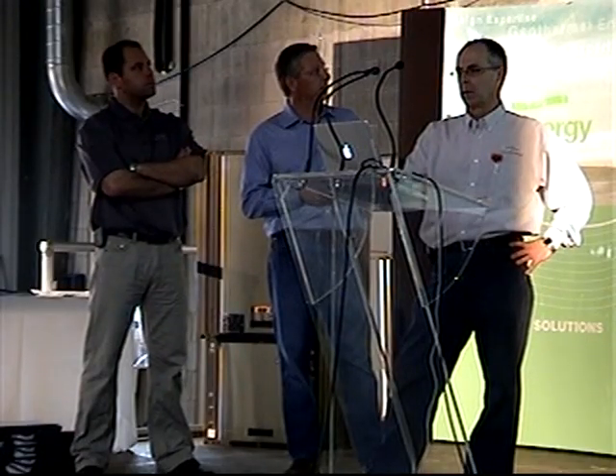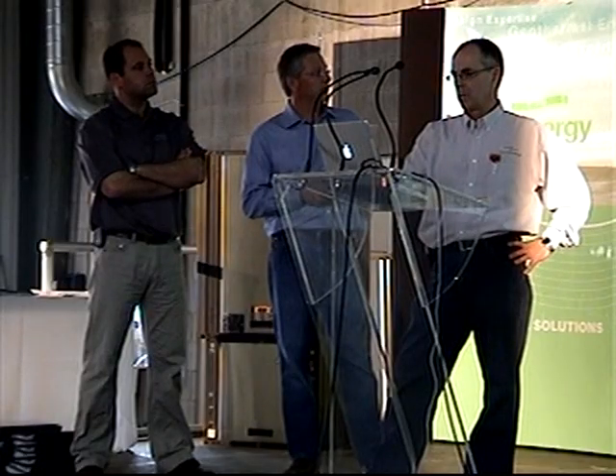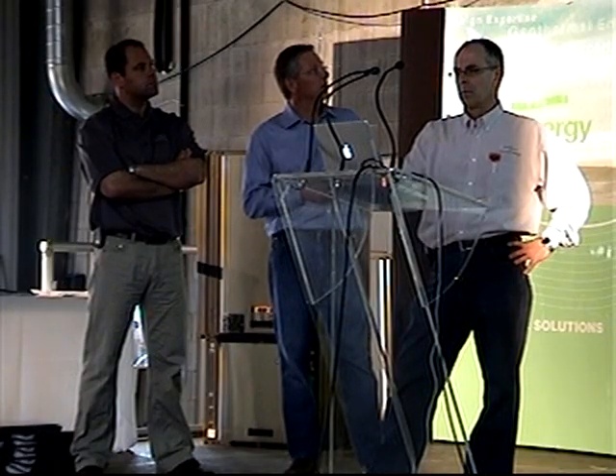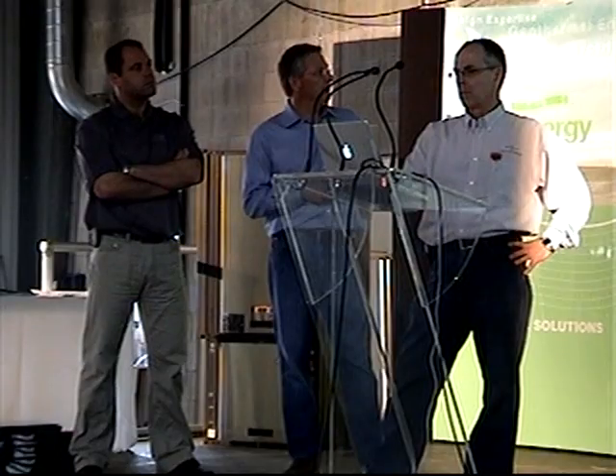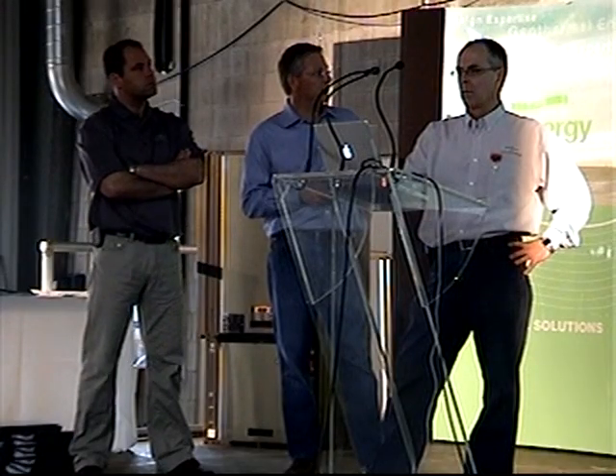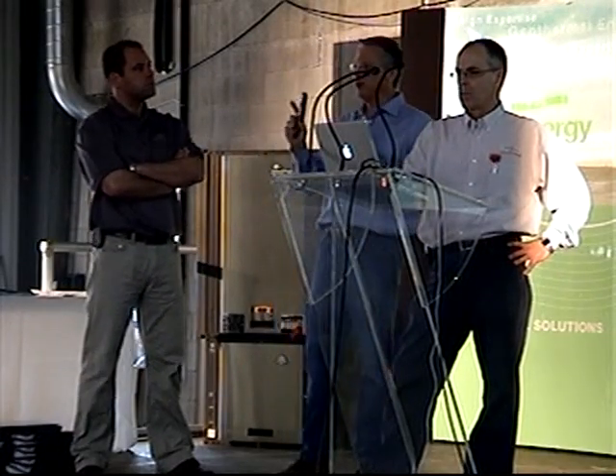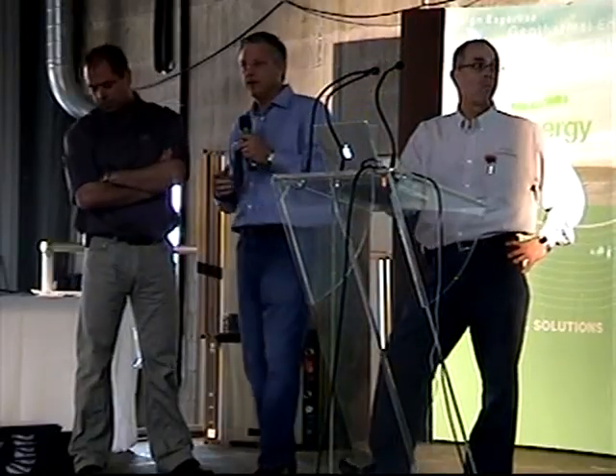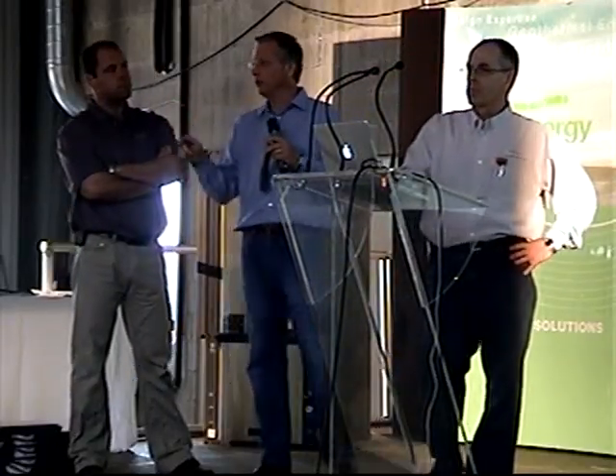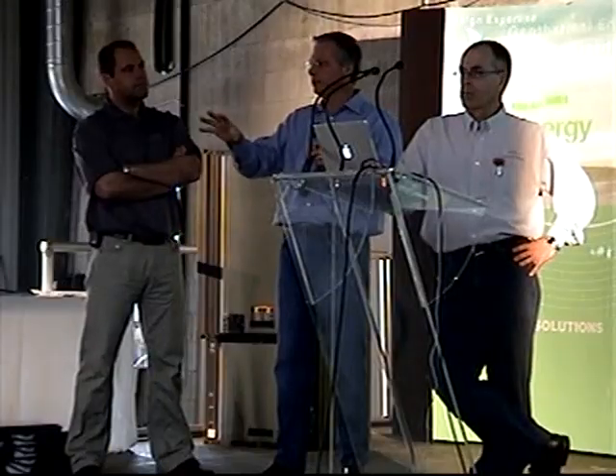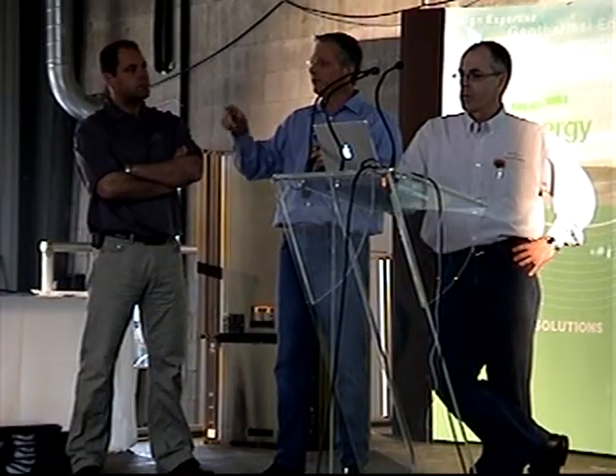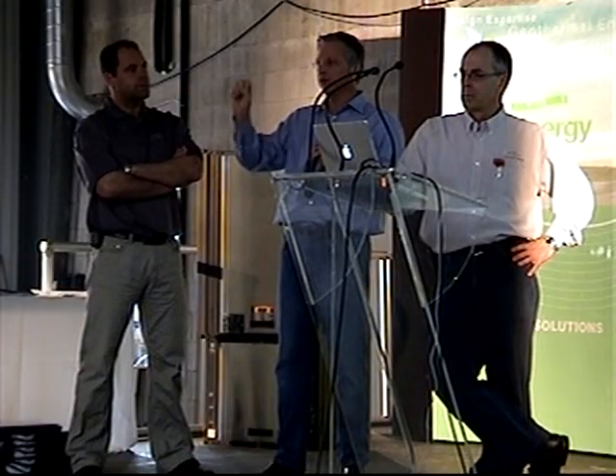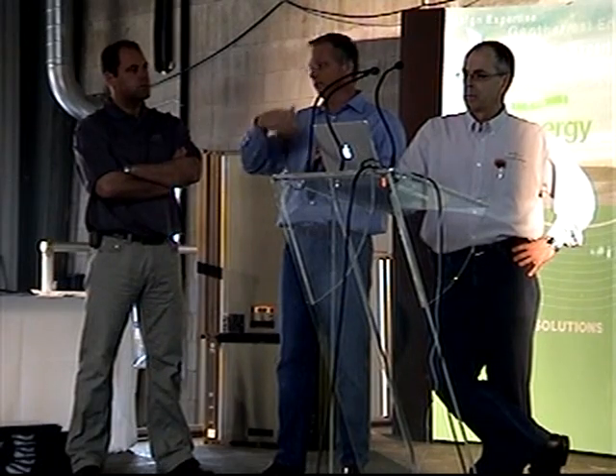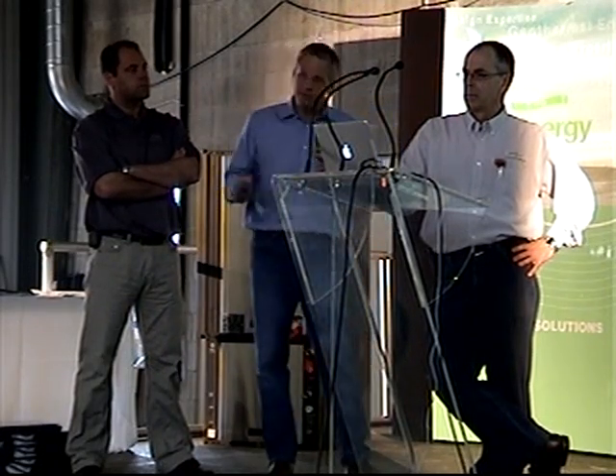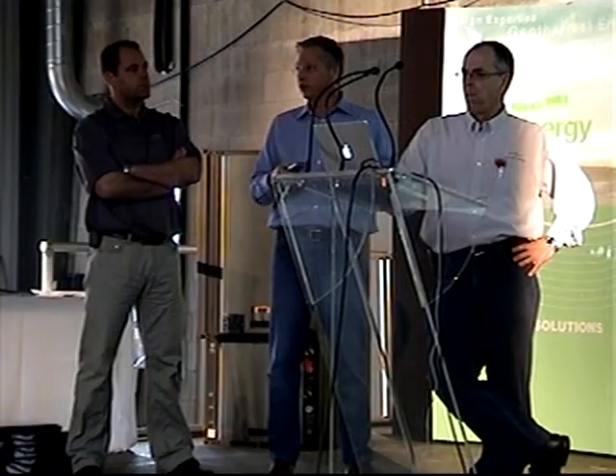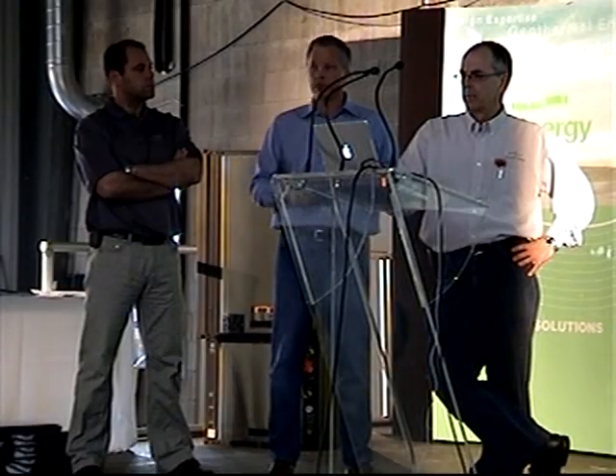Let's go back to the table or the IOM. Let's go through a few of these. Okay, so what happens when you go to test mode? By the way, when you do the 3 Gs on and off at the thermostat, that's the same thing. You're throwing the unit in test mode. So you can be standing in the house at the thermostat, not want to wait that time delay. Just turn the fan on and off 3 times, get it thrown into test mode, and you don't have to wait on time delays. You don't have to run back to the unit to do this. You can short those 2 pins, or you can do it at the thermostat.